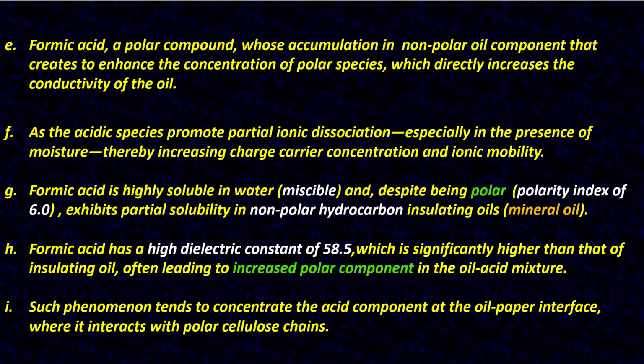Formic acid has a high dielectric constant of 58.5, which is significantly higher than that of insulating oil, often leading to increased polar component in the oil-acid mixture. Such phenomenon tends to concentrate the acid component at the oil-paper interface, where it interacts with polar cellulose chains.